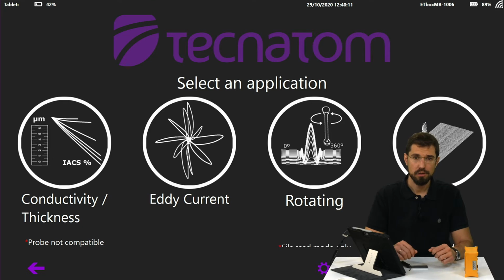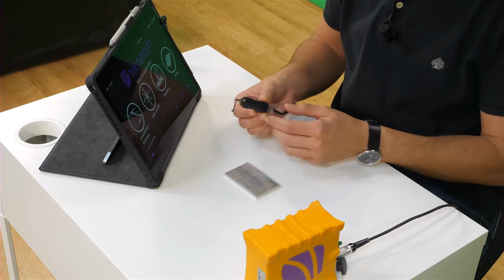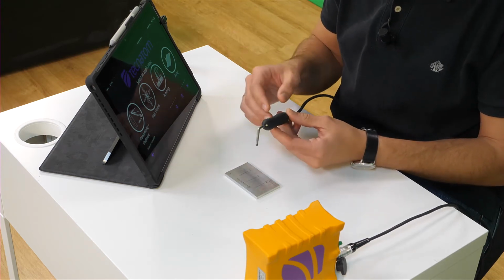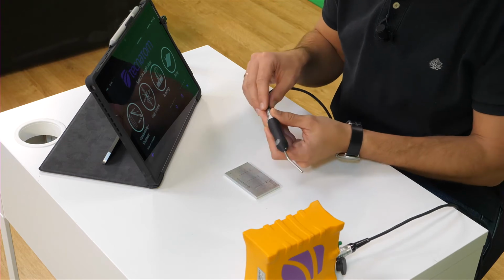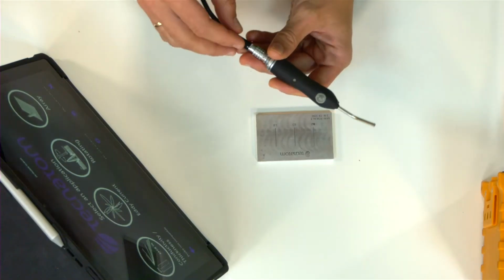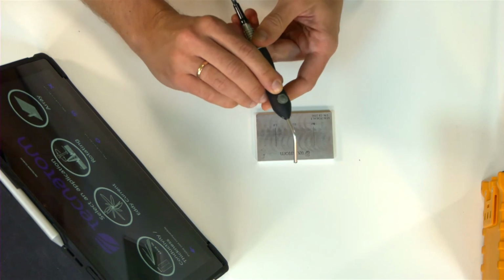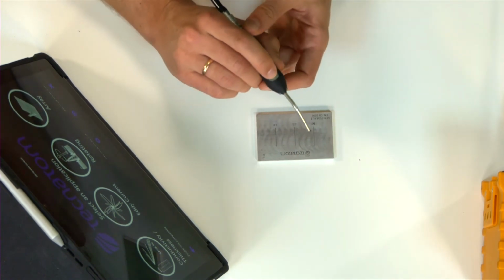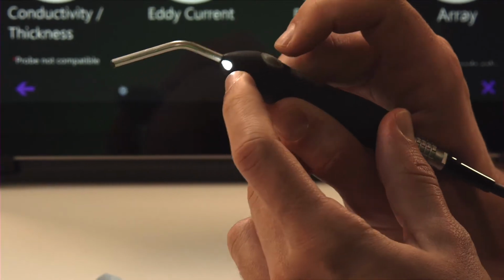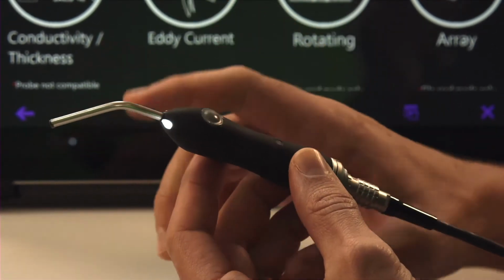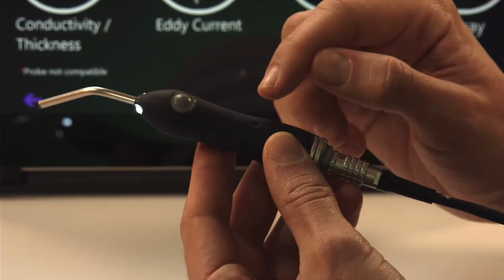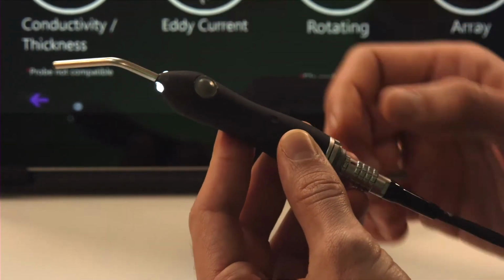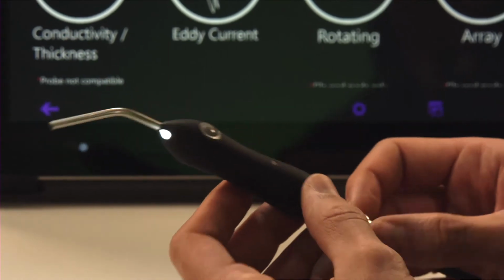I'm going to do a demo where, with a basic setup, we'll do a calibration and acquisition of this calibration block with 3 notches. To do so, we're going to use this pencil probe. It's a probe developed by Tecnatom, whose work range goes from 500 to 1000 kilohertz. It has a push button, so in this case, we've set it up so that we can use a long push to turn on the LEDs and the short push to do a hardware null. It also has a small LED that lights up when we have configured our alarms.